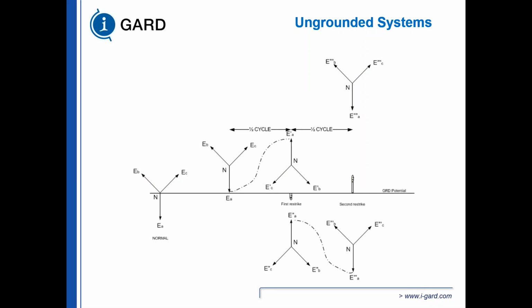Because neither the neutral nor the phases is connected to ground, when you get a ground fault, and we're going to assume here that the ground fault is on A phase, A phase and ground are at the same potential. 1/2 cycle later, you're at 2 per unit above ground with A phase.